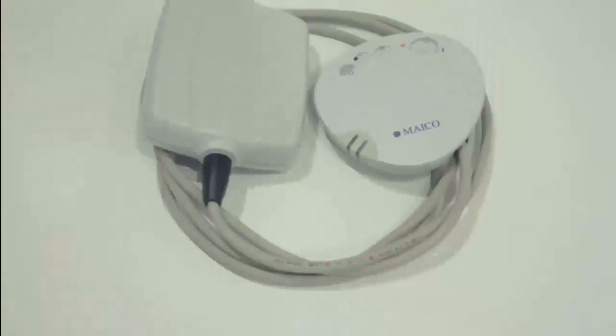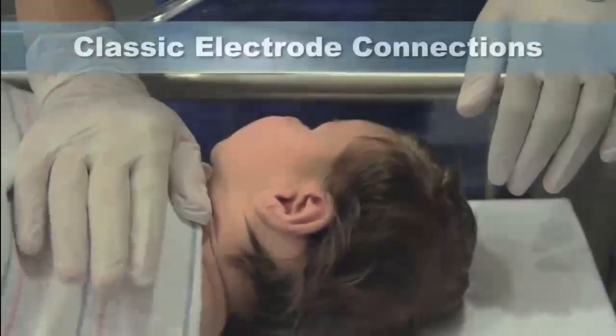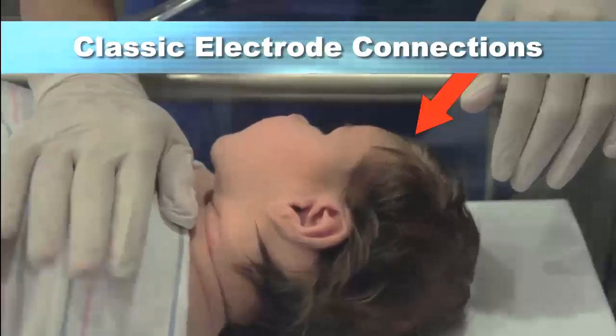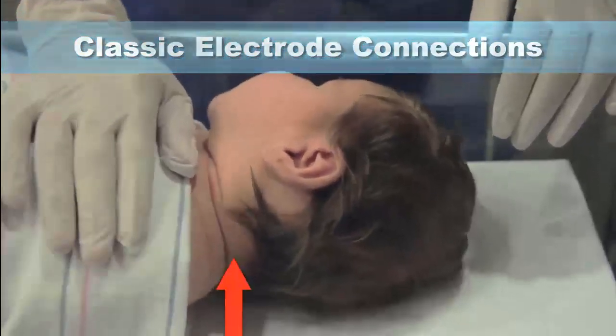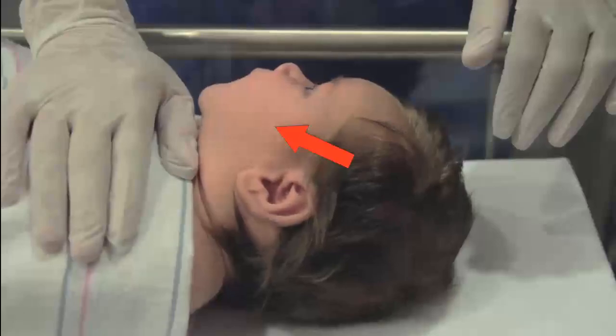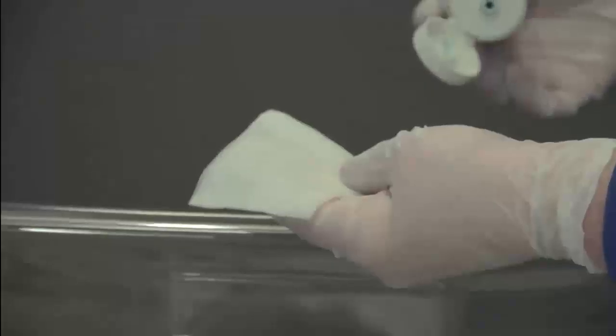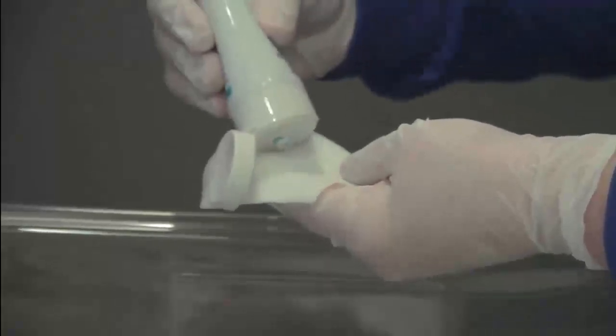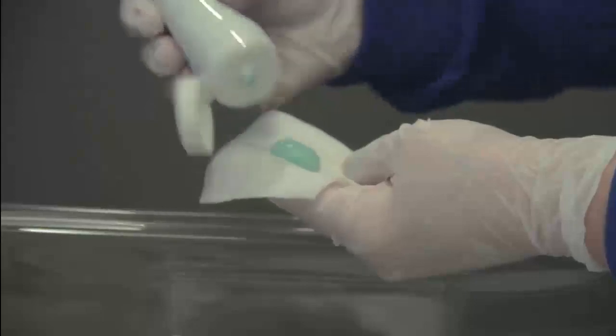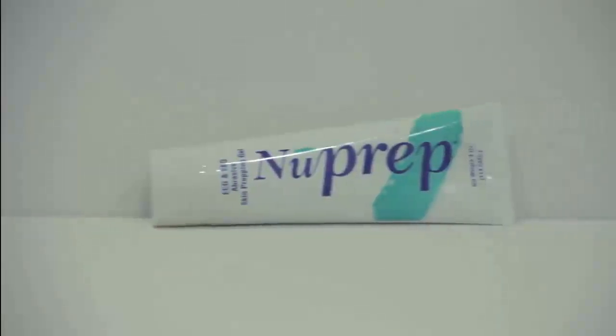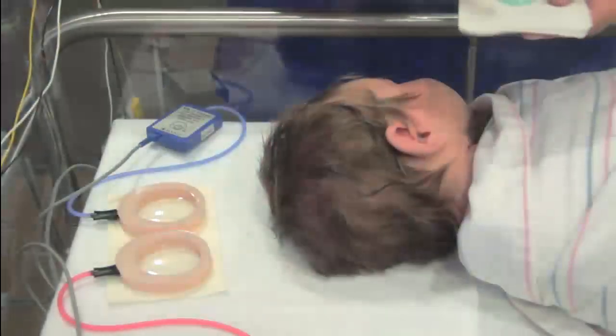For screening with the MB11 Classic, the electrodes should be placed on the center of the forehead at the hairline, on the nape of the neck, and on the cheek. Before placing the electrodes, the skin at these locations must be prepared by cleaning them with an electrode skin preparation product such as NuPrep or an electrode skin prep pad.